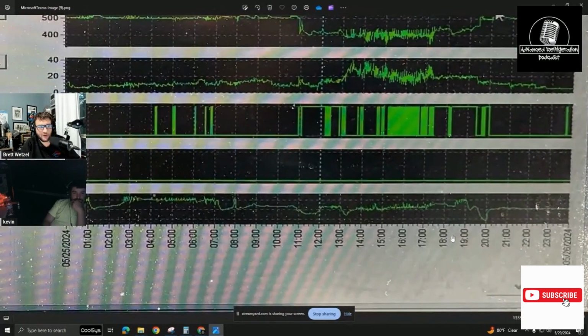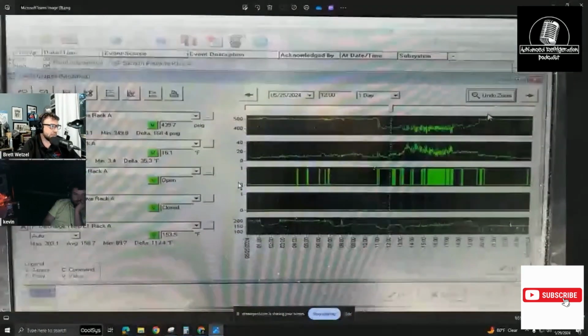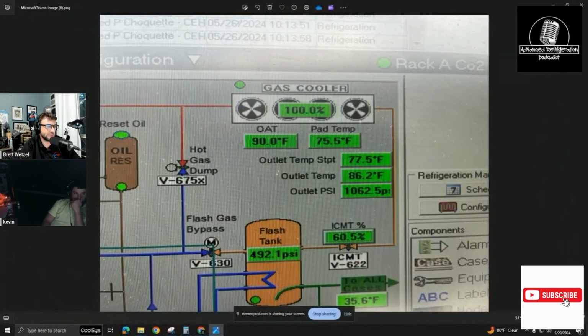And then this is when I had the epiphany. I was like, something has to be shutting off, because it kept failing around 6 o'clock or so, somewhere in that range. And you can see that right here, the discharge temperature basically dropped all the way down because the system went in defrost. When that happened, this is what I was talking about, the no-no zone. Basically went below the 18 degrees that it was set for, dropped down to about 15. That's when I think it started oil failing. But I think mainly because his hot gas wasn't barely feeding.